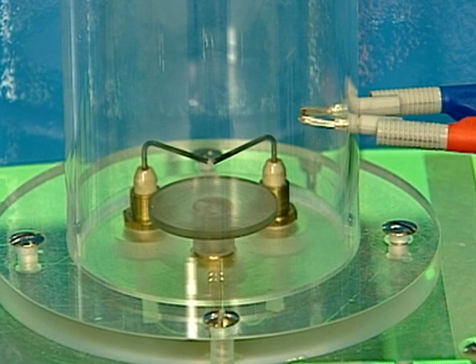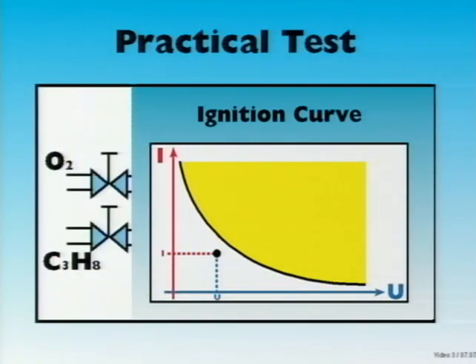The ignition energy caused by electrical sparks decides the existence of an explosion. If below the limiting curve, then no ignition of the gas occurs. If above, then an explosion takes place.